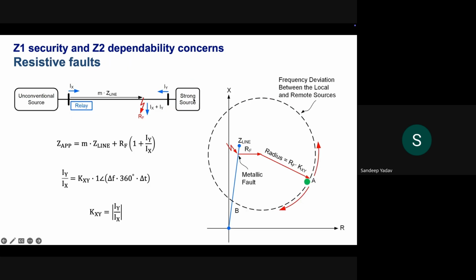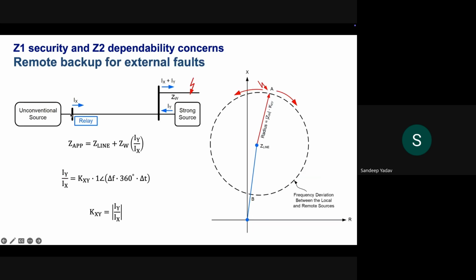For an external fault, so this is the line from X to Y, and there is a different line, and this is an external fault to this line. Same, in this case also, the impedance would be the Z line, the complete line length, plus ZW, which is the impedance of this line, into IY by IX. So again, depending upon the type of current, the behavior of IY and IX, the impedance seen by the relay could be anywhere on this dotted periphery.